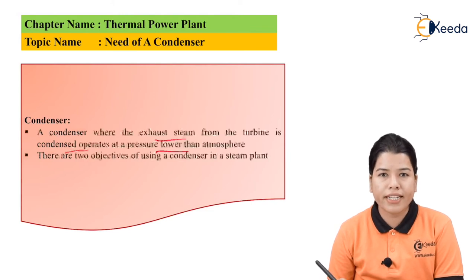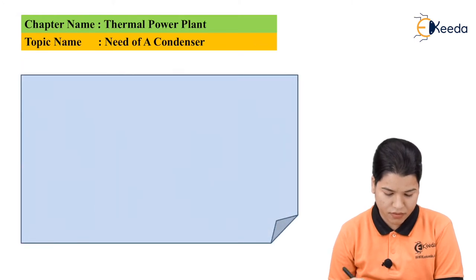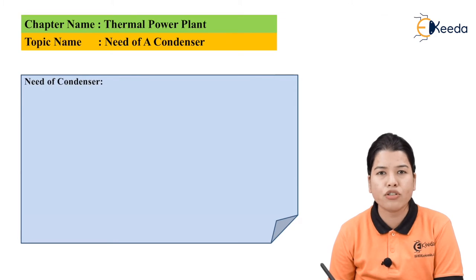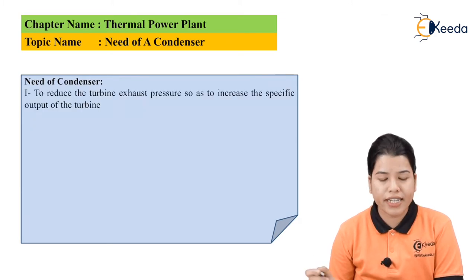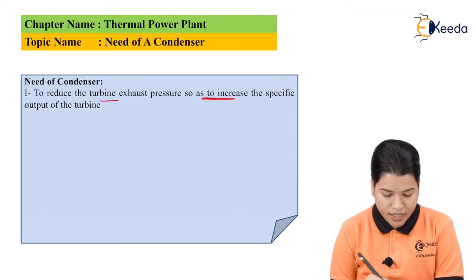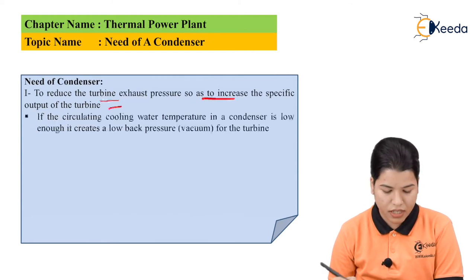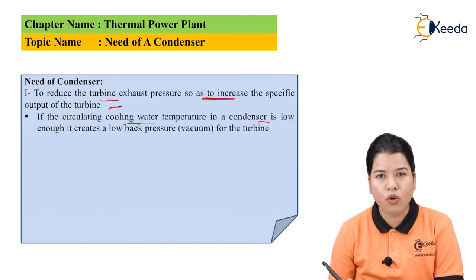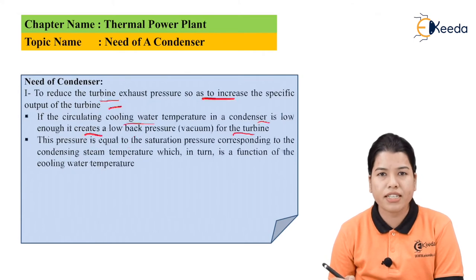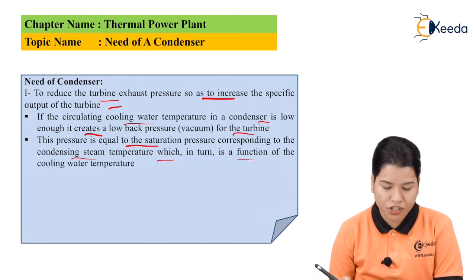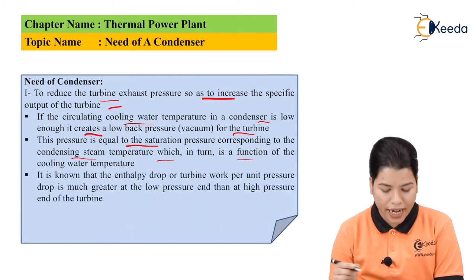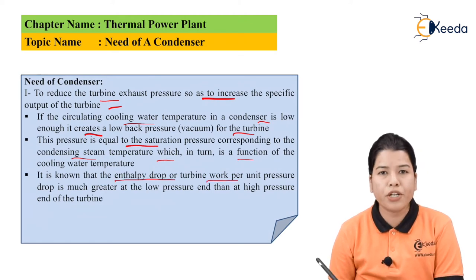There are basically two objectives of using the condenser in the thermal power plant. The first need is to reduce the turbine exhaust pressure so as to increase the specific output of the turbine. If the cooling water temperature in the condenser is low enough, it creates a low back pressure equal to vacuum for the turbine. This pressure is equal to the saturation pressure corresponding to the condensing steam temperature, which in turn is a function of the cooling water temperature. The enthalpy drop or turbine work per unit pressure drop is much greater at the low pressure end than the high pressure end of the turbine.